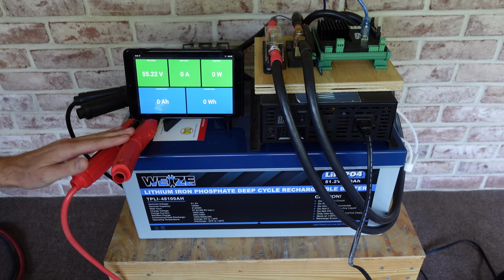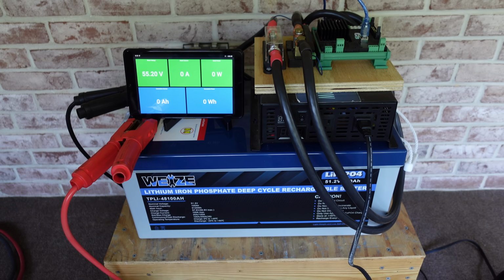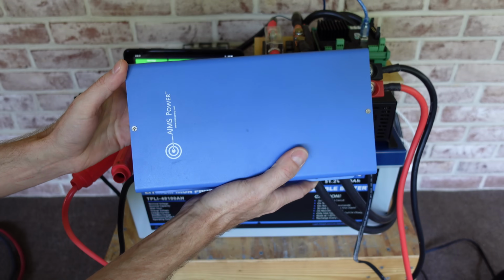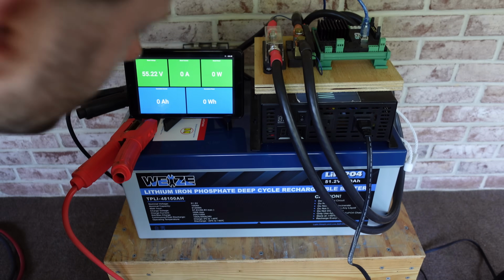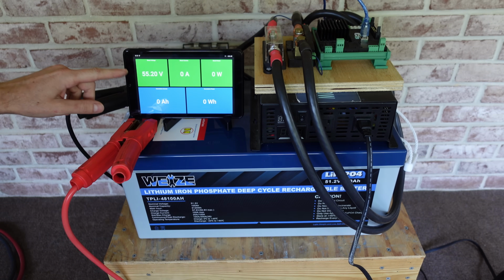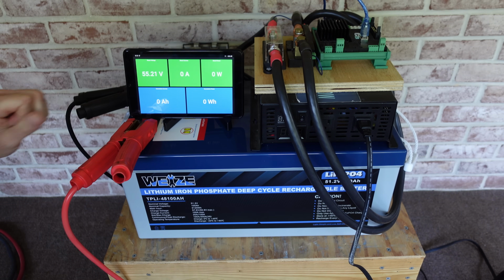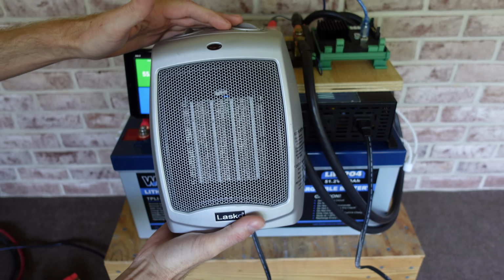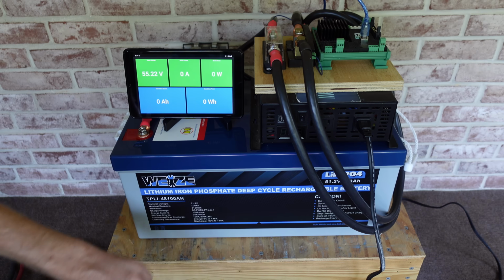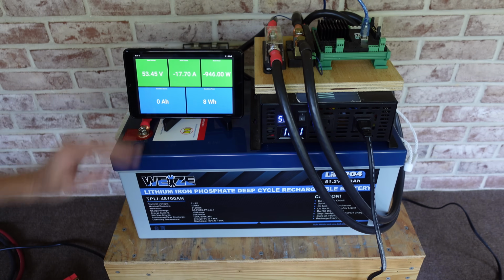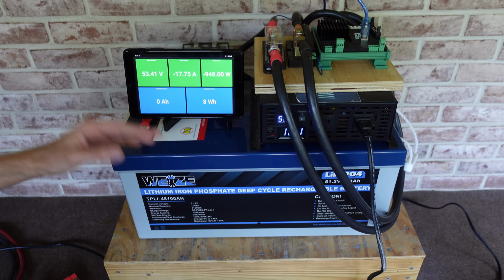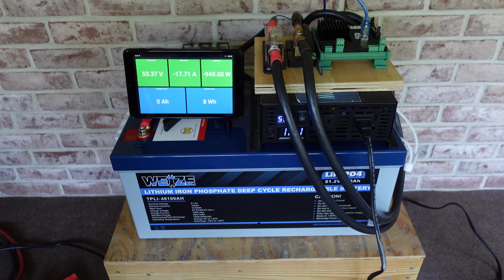Alright, so we're hooked up to my standard capacity testing setup here. I charged this battery using an AIMS lithium iron phosphate rated charger, and you can see we're sitting around 55.20 volts. It's been floating like this for about a day and a half now, so it's had a little bit of time to balance. My test load will be the space heater on low, pulling approximately 980 watts. So here we go. We'll leave this running until the BMS in the battery stops the test, and we'll see what our measured capacity is.